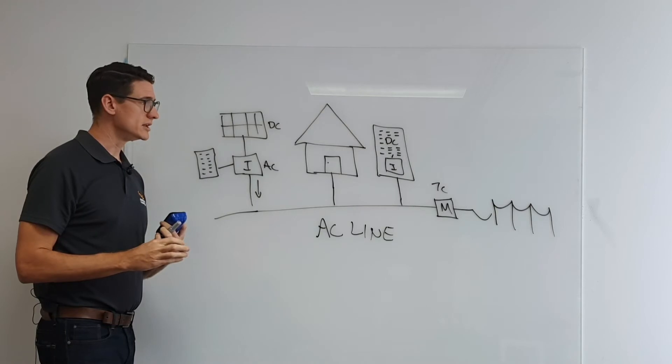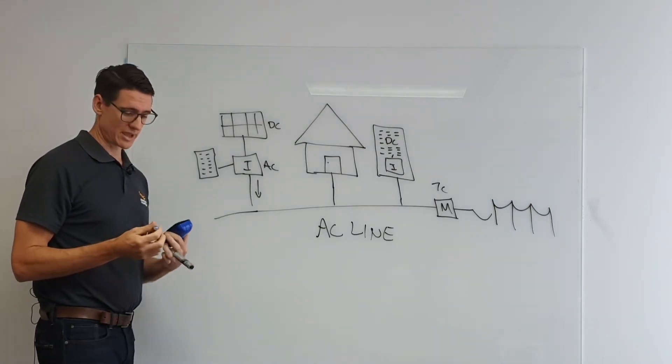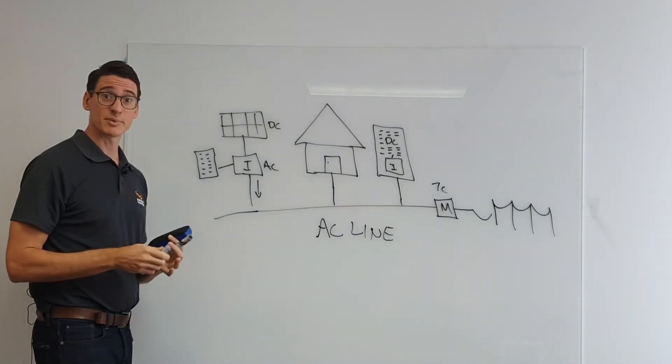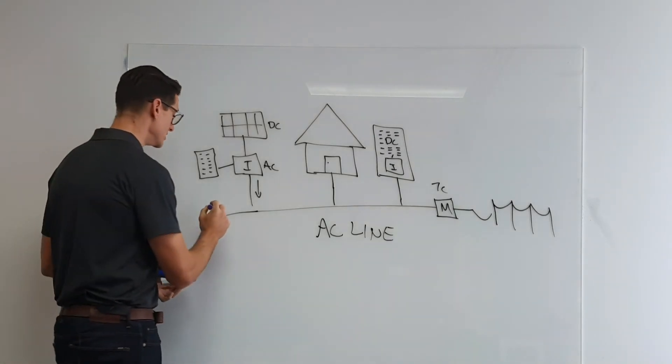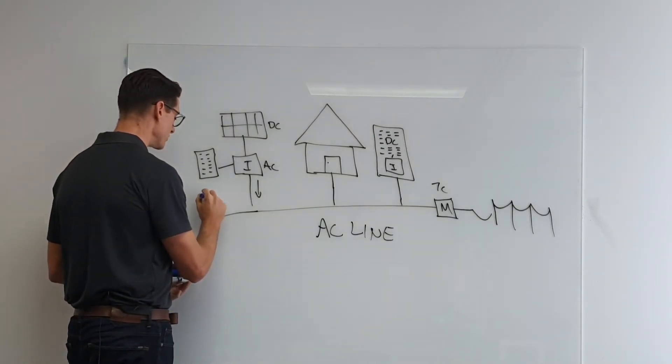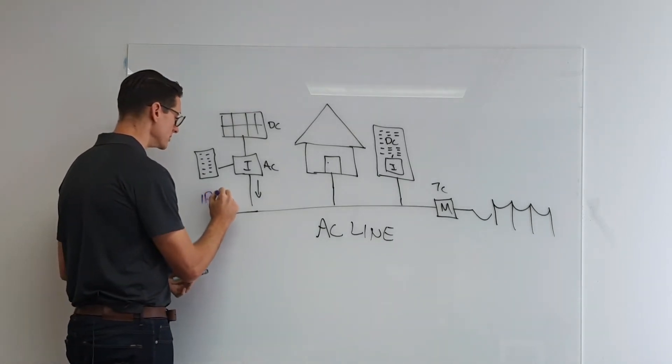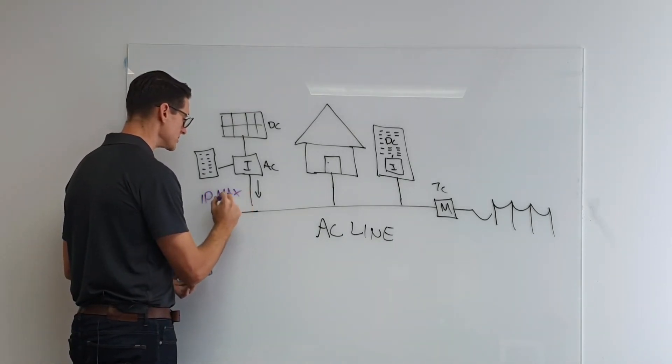So in Western Australia, we have a network operator, Western Power, has a rule that if you have a single phase home, your maximum allowable inverter capacity is five kilowatts.